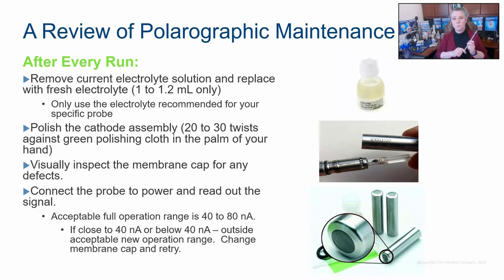If it's not, what can you do? You can go back in and replace the membrane cap. These get replaced every 2 to 3 months. Try it again: polish the cathode, fill it with electrolyte, and check it again. It didn't go up. All right. The next thing you can replace is the cathode assembly. Not all probes allow you to replace the cathode assembly, but some do. If you can, then replace the cathode assembly, because these will die over time as well. Add the electrolyte, screw it together, and check it.